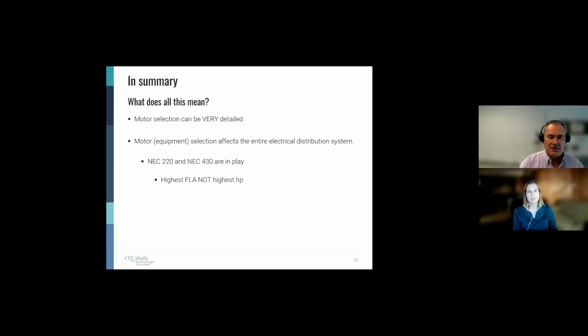It affects the entire electrical distribution. We have to read NEC 220 and understand it. Same with NEC 430. And we have to understand that there's a difference between high horsepower and high full load amperage. Okay, we need to make sure we know what we're talking about, because NEC is concerned with full load amps, not the biggest horsepower. Historically, we've always assumed that the biggest horsepower has the biggest full load amps, but if you have some bad motors, maybe that's not always the case.